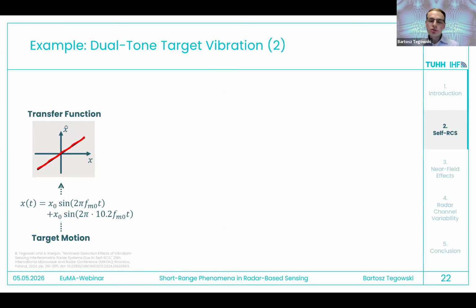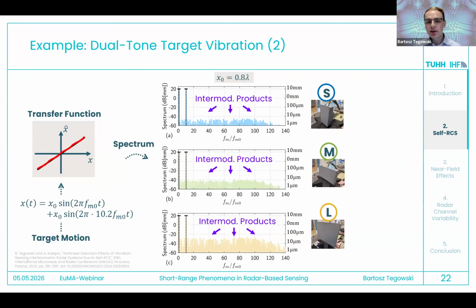In the second example, this is also very interesting because, since we are dealing with a nonlinear system, we also observe some intermodulation effects, mechanical intermodulation effects. So we assume the target is moving with a dual tone motion, where both of the oscillation amplitudes have equal mechanical amplitudes, but they vary in frequency. And the response we get is a lot of intermodulation products, even at 100 times the fundamental oscillation frequency. This is due to the Bessel shape of the spectra, which can generate higher order harmonics, which then show up in the intermodulation with a very large mixing order.